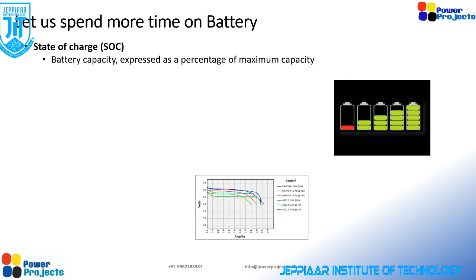The maximum SOC is 100%, minimum SOC is 0%. If SOC is 50%, that means the battery holds 50% of what it can hold. In lead acid batteries we may not access till 0% and up to 100%, but in lithium ion batteries it is possible to utilize the entire 100% of the energy available. But for that you cannot use a constant power charge or discharge. Above a certain SOC, the charging or discharging mechanism has to change automatically if you want to extract the entire capacity from the battery.